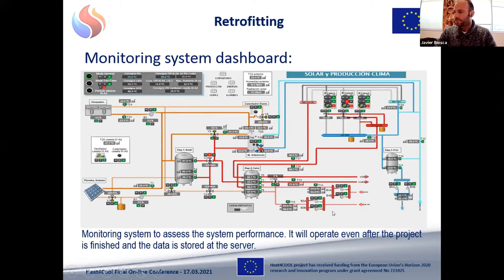As you can see in this monitoring system, we can see the temperature at several points in the facility. And also we can control several components as the three-way valves and the old heat pumps or the absorption unit. This monitoring system allows us to assess the system performance, and it will operate even after the project is finished and the data is stored at the server.